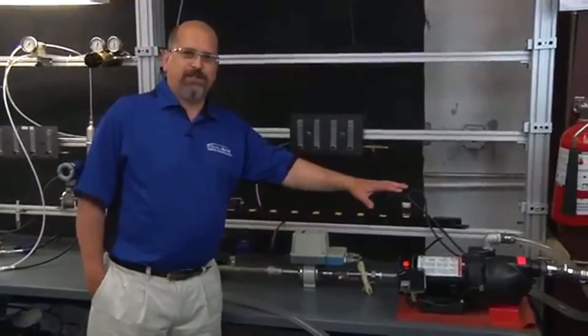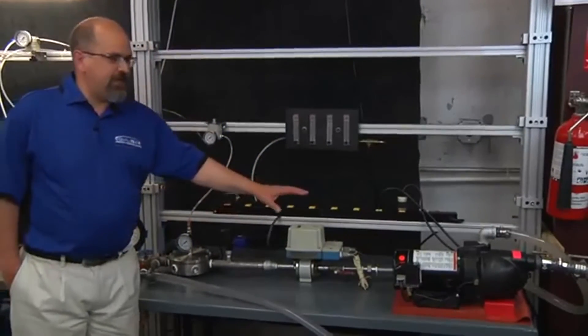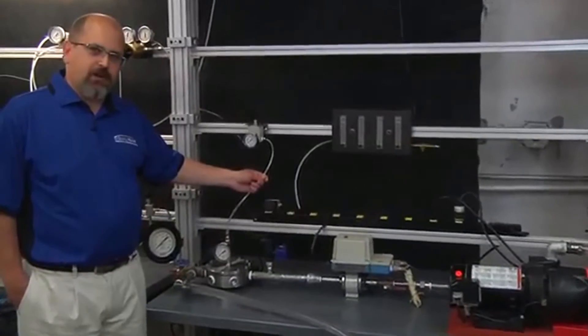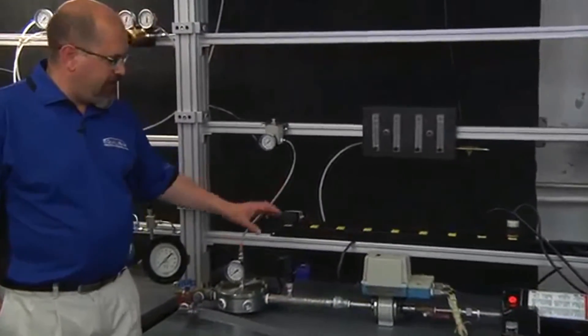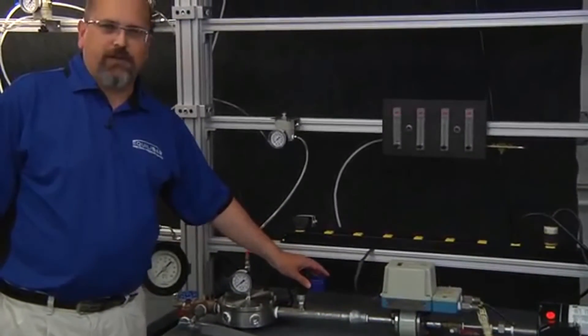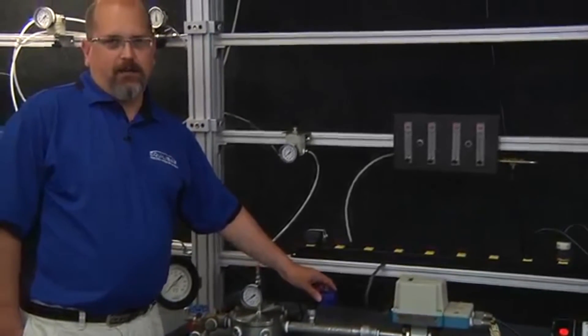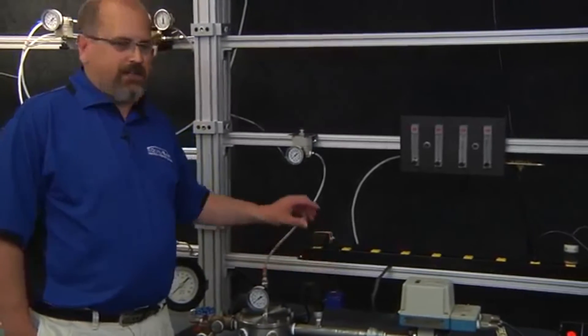We've now powered up the pump and we're flowing water through the system. To set the flow rate, I'm going to adjust the pilot pressure on the Equilibar Back Pressure Regulator. That's going to control the pressure on the output of the pump and it's going to let me set the pump on the flow curve until I get the desired flow.